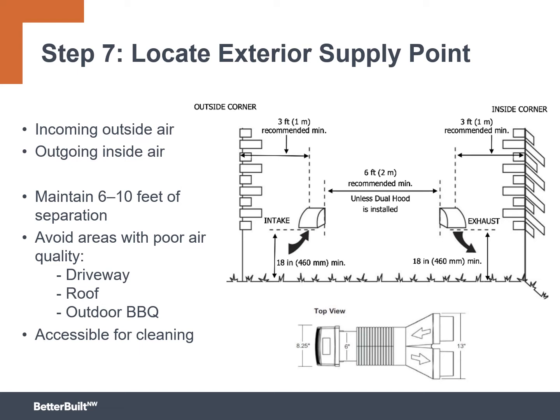And finally, again, we're going to talk later about maintenance and homeowner operation. Make sure this is accessible for cleaning, especially the intake. You've got a mesh screen on there. Over time, new outdoor air being sucked in over and over and over with pollen and dirt and animal hair, all those things, it will eventually get clogged. So a basic piece of maintenance is being able to get access to it. So again, as I said, roofs are not a good idea. 12 feet off the ground is probably not a good idea. If you can think about it, 2 to 5 feet off the ground in a good location, that's ideal.